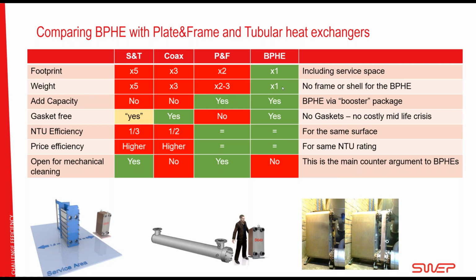Weight, again, the brazed plate is a clear winner, at minimum 2 and upwards of weight per BTU. The possibility to add capacity: both the shell and tube and coaxial are made to that capacity. You could add some extra tubes in a shell and tube, but it's still made based on how many tubes you can fit in it, right? With a plate and frame, you can open it and put inside extra plates. And with a BPHE, you can have a booster package with a standard capacity, and then a booster package to add capacity. Gasket free. Gaskets are not a good thing because they degenerate over time.